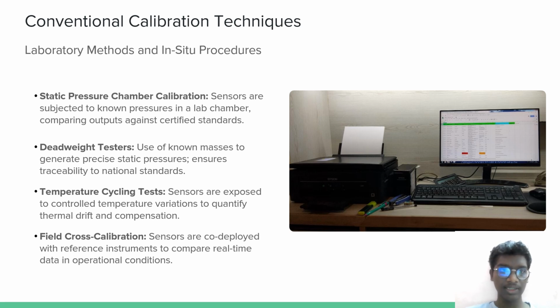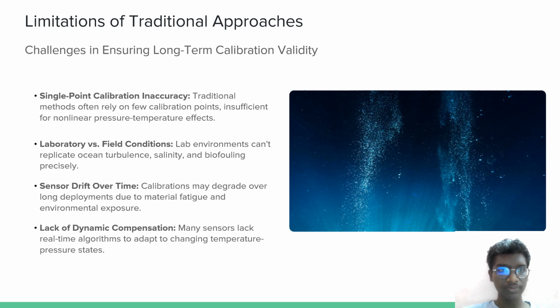Conventional calibration techniques: laboratory methods and in-situ methods. Static pressure chamber calibration: sensors are subjected to known pressures in a lab chamber, comparing output against a certified standard. Deadweight tester: use of known masses to generate precise static pressure, which ensures traceability to national standards. Temperature cycling test: sensors are exposed to controlled temperature variation to quantify thermal drift and compensation. Field cross calibration: sensors are co-deployed with reference instrumentation to compare real-time data in operational conditions.